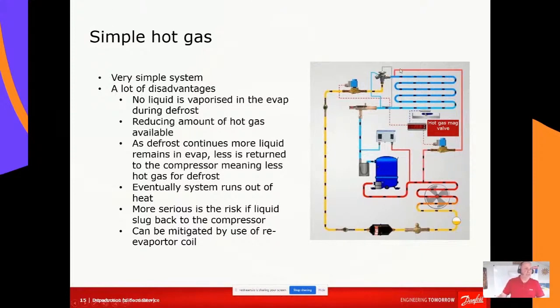Because we're putting hot gas into the evaporator here, it's condensing back to a liquid. We're not really going to put a lot of vapor back to the compressor. So in essence, the system runs out of hot gas. It's okay for a very quick short burst of hot gas to the evaporator, but you will eventually run out of hot gas because you're not getting any vapor back to the compressor to compress.